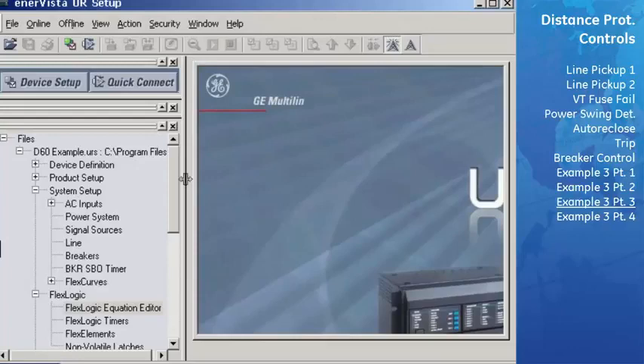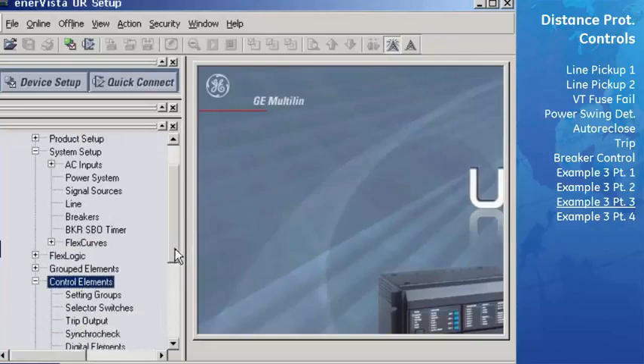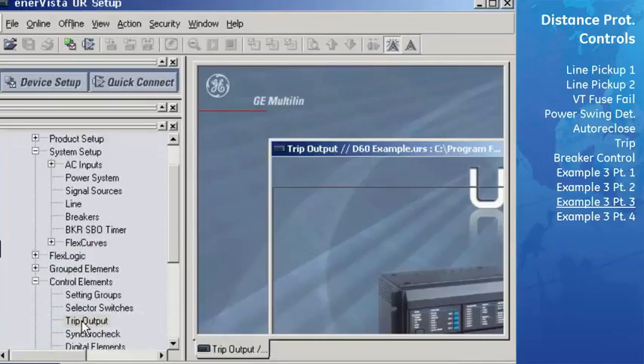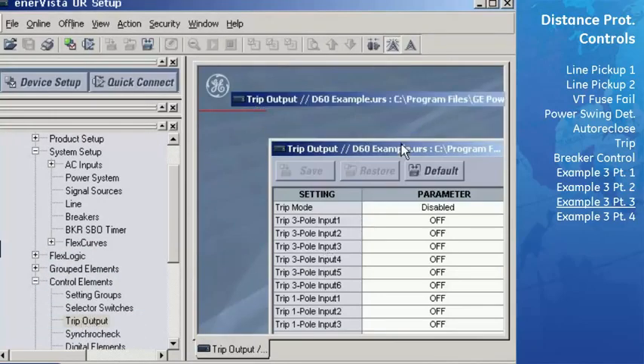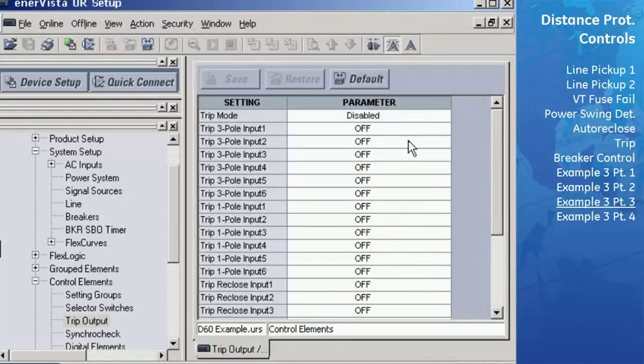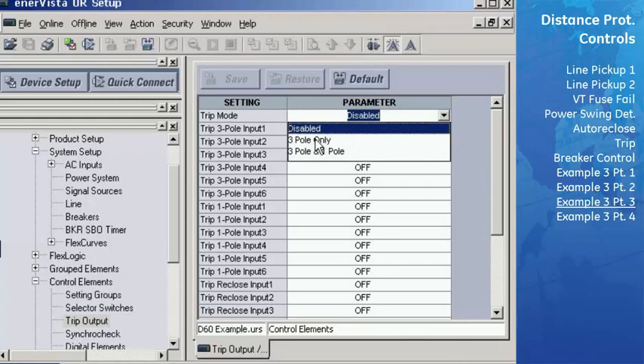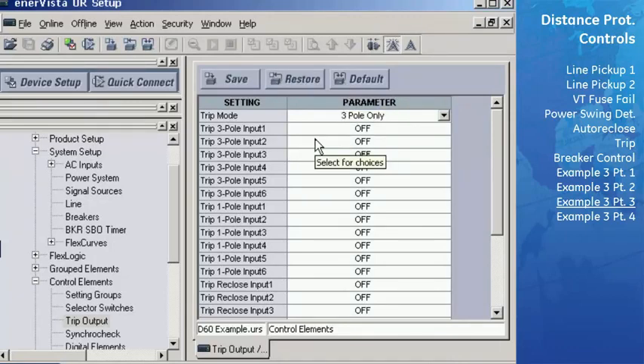Now we'll configure the trip output function settings. Go to Control Elements, Trip Output. Change the trip mode field to 3-pole only, since only 3-pole tripping will be used in our application. In the trip 3-pole input fields, we need to set all the different reasons we would like to trip all 3 phases of the breaker.